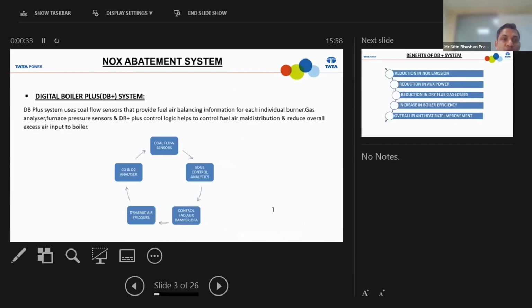Basically, I will be telling about the NOx abatement system that we have implemented in Unit 4 just before our ASD. This is a kind of digital boiler system which is provided by GE. In this system, they have placed coal flow sensors all over the coal mills, collecting data, and it is used to control the FAD, basically the fuel air dampers, auxiliary damper, and with the dynamic air pressure, it is controlling. It also has CO and O2 analyzers.